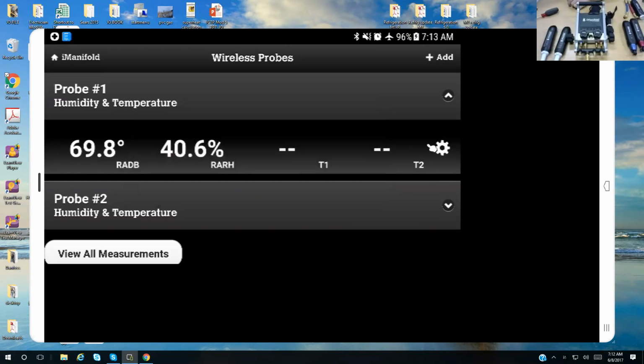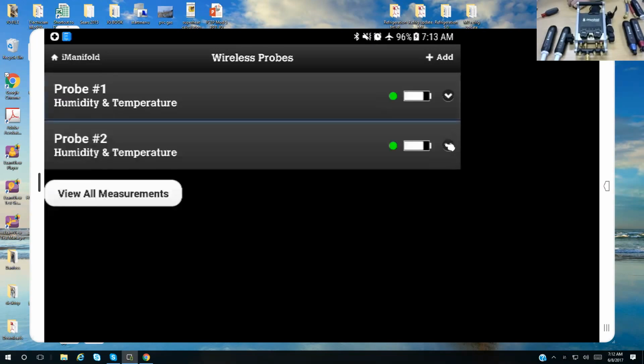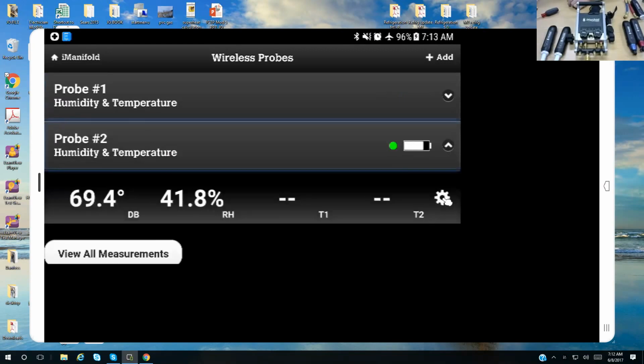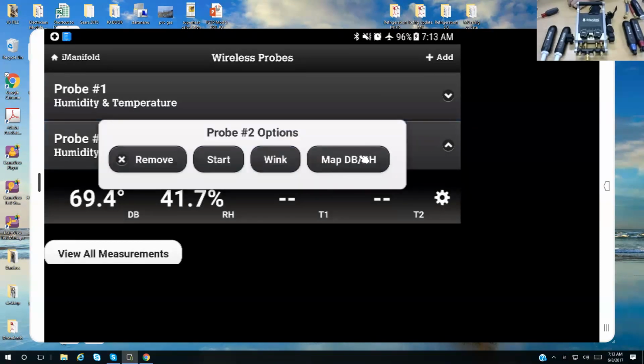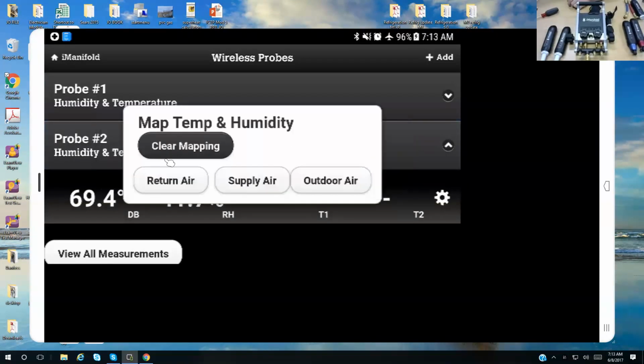And then we're going to change the others. Here we are at supply air dry bulb, supply air relative humidity. And then I'll bring up probe 2 and change it over to the return. I'm going to tap on the little menu here. I'm going to choose the map option. And I'm going to map it as the return air. And you'll see it change over to return.